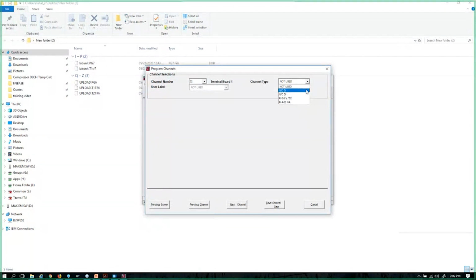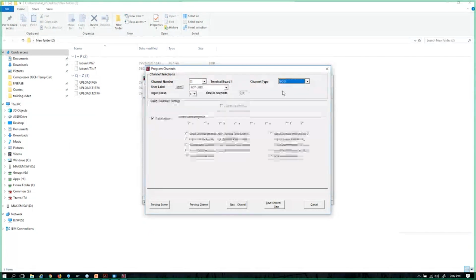We have a normally open or a normally closed. Now, last week when we covered the hardware, we should have talked about the 2 different ways to wire up in-device switches, normally open or normally closed. And it's just either we have a jumper wire installed between the 2 terminals for that channel number or we don't. That's that simple. Changing the system from normally open to normally closed here in the software really does not do anything. But there is a section in here where we can print this program or get about a 4 to 5 page report from this program that will tell us this information.